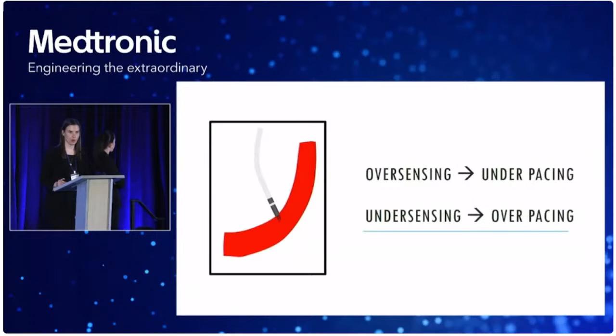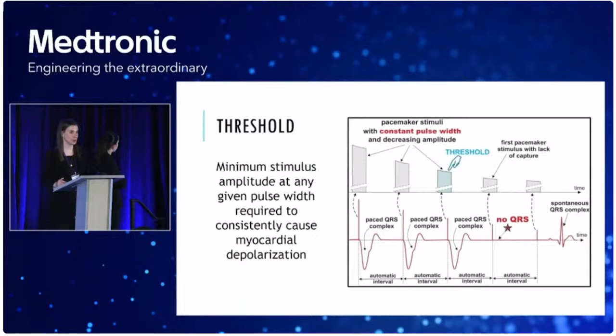Well, what about threshold? So a threshold is the minimum stimulus amplitude at any given pulse width required to consistently cause myocardial depolarization. So we tend to decrement the amplitude, and we look for when we lose capture. And then our threshold is when we were last consistently capturing the myocardium. So you have to be watching what you're doing while you do that test. It's a little scarier when the person's pacemaker dependent. You want to watch really well because you don't want to make them black out.